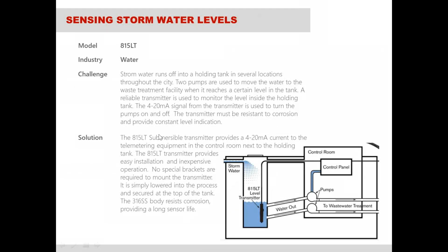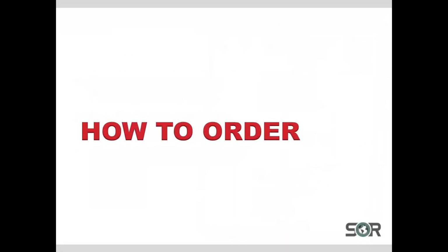Another application is for sensing storm water levels. In the sewer systems, where the rainwater is collected during heavy storms, you have to monitor the level to operate pumps to properly pump that water out of the sewer system into somewhere else, so it doesn't flood cities or residential areas and so on.